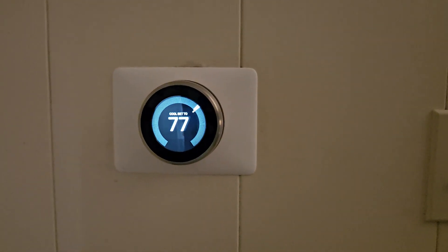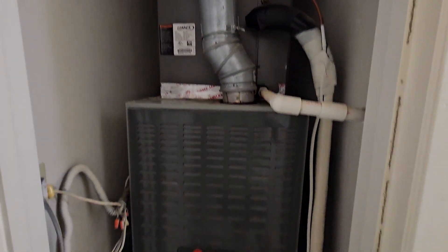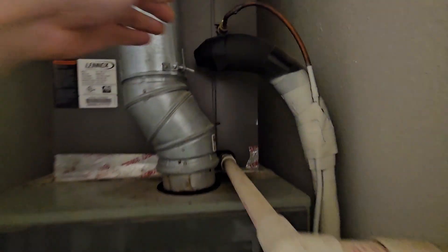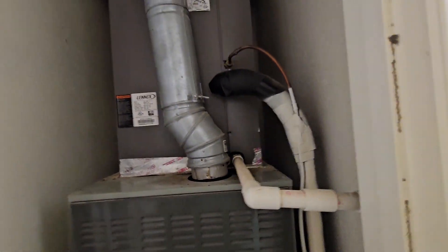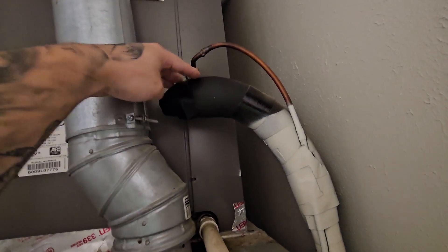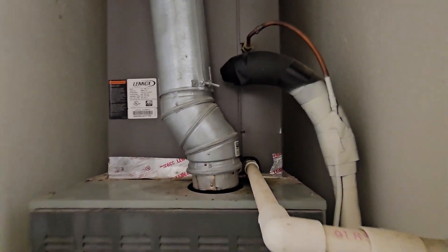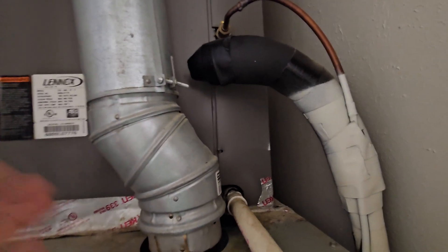The install is pretty quick and you'll be skating along pretty good, and then all of a sudden the AC is not gonna be working. After two techs came out and tested the unit, nobody could figure out what was going on. The fan was blowing but the compressor almost felt like it was going into protect mode. One of these pipes is high pressure, one is low pressure — they run to the outside compressor unit. It was still blowing but not blowing cold, no condensation, no sweat on the pipe.